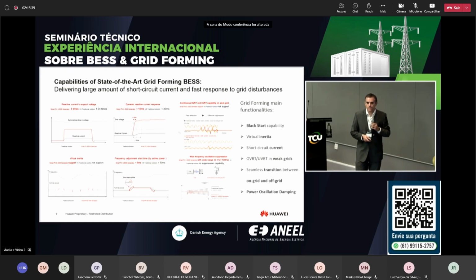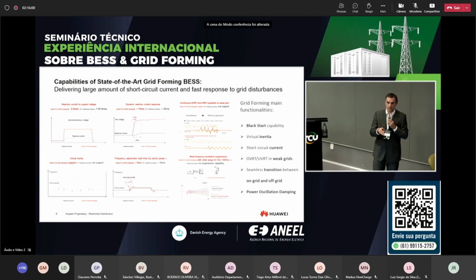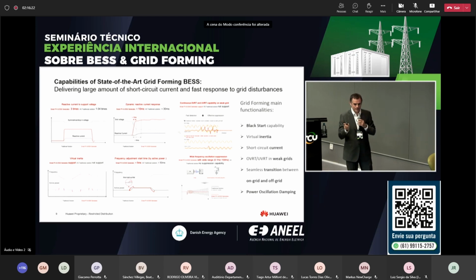The traditional solution, I don't know if it's a standardized term, but I call it the grid following solution. It reads the voltage, calculates things, and puts current based on it. If there is no voltage, this solution won't work, because there's no voltage to put current on. In some cases it could result in an undesired island, which would be complicated, undesired operation. But mainly, that's the difference: one needs the voltage to put the current on it, and the grid forming will create the voltage. That's the main difference.